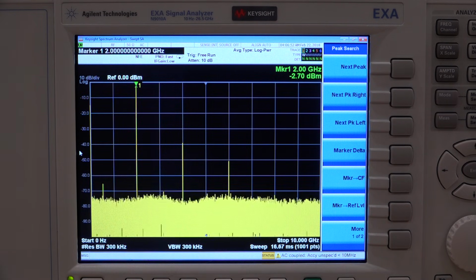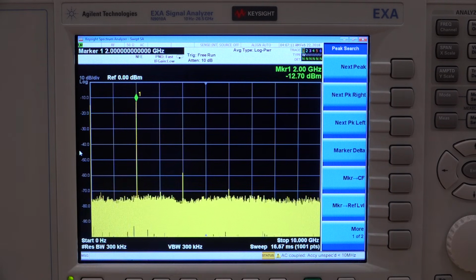And I'll demonstrate that. I'll change the power from 0 to minus 10 dBm. And check it out. You can see that it went down by exactly 10 dB. So it's very accurate. And all the other harmonics went down even more. So this linearity seems to be coming from the final output drivers on their synthesizer. So it's really quite good.